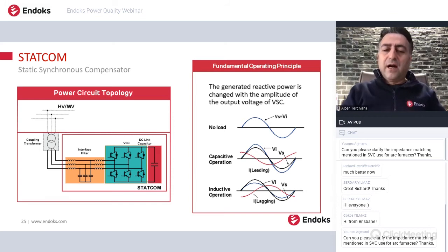STATCOM is like a UPS in our offices, in our houses. We are using uninterruptible power supplies. Actually, STATCOM is working with the same converter topology. But here, STATCOM's main responsibility is generating reactive power, not active power. A UPS can inject active power, can create active power, but a STATCOM is generating reactive power. Hence, a STATCOM does not need any power on the DC side.